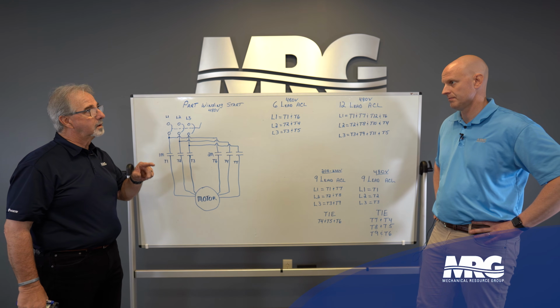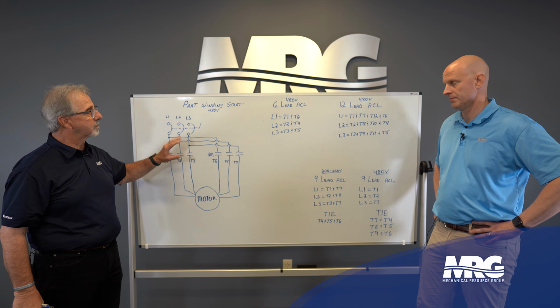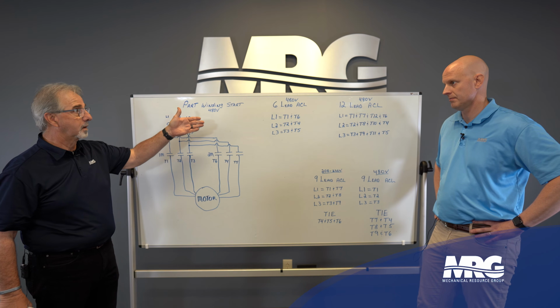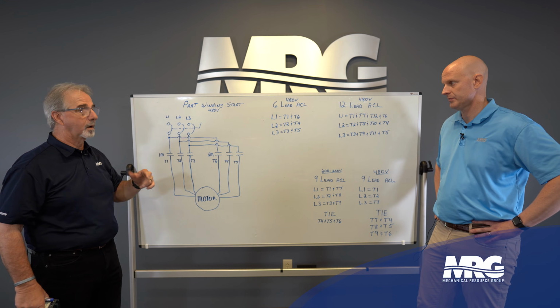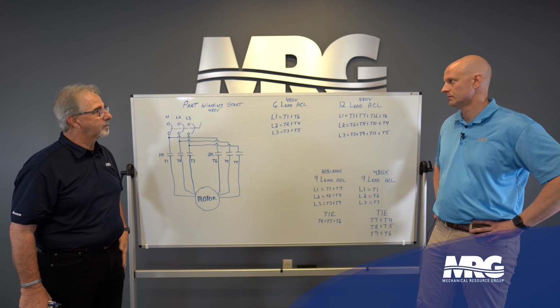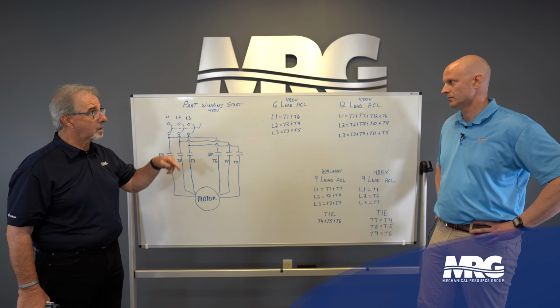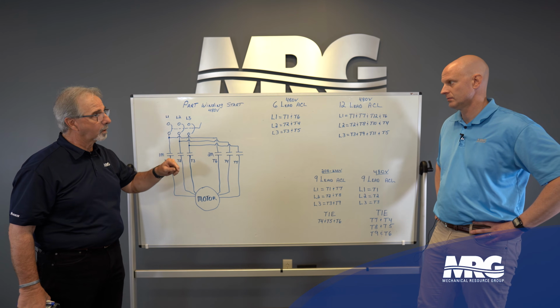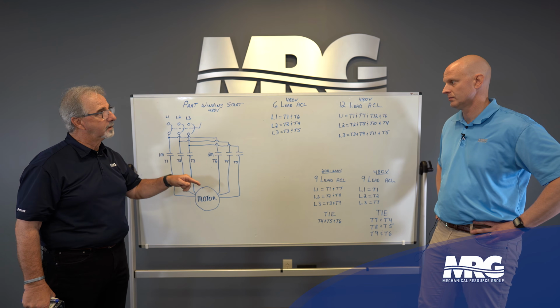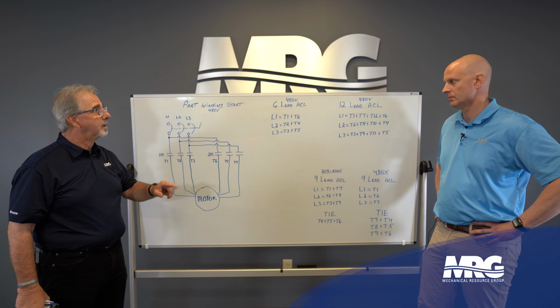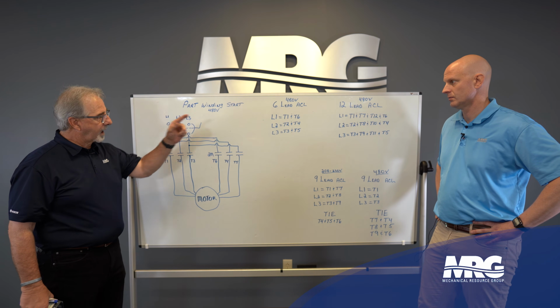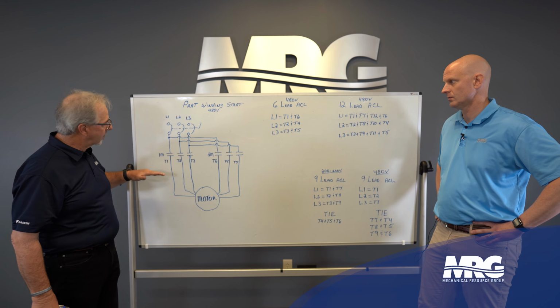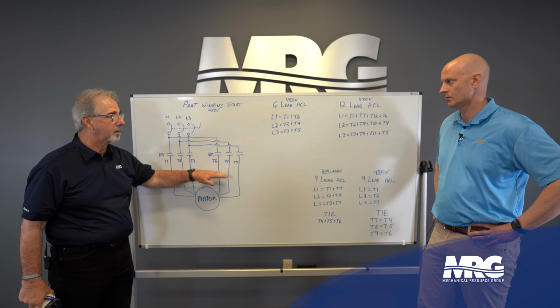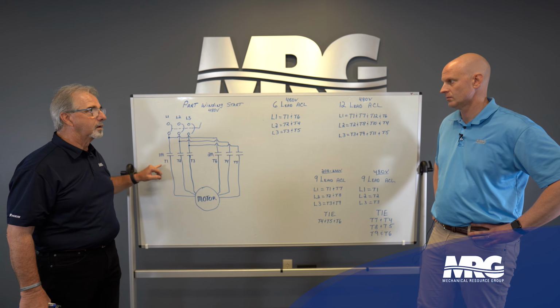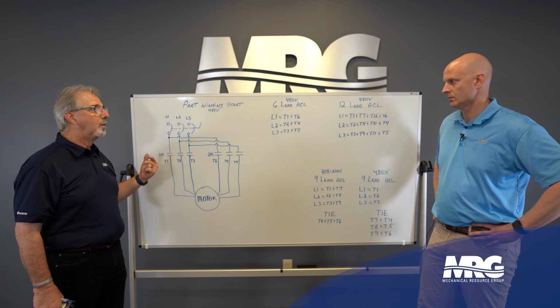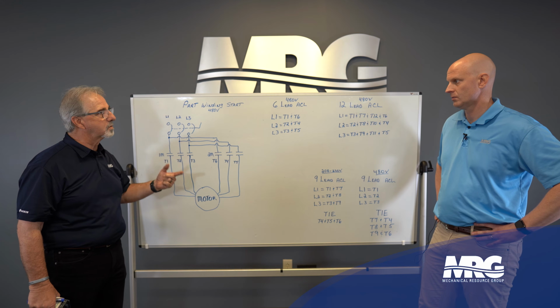What's important is that you understand this is on a 6-lead motor or a 12-lead motor. So I've given you across the line connections. If I was going to start this 6-lead motor across the line with a single contactor, L1 would be motor leads 1 and 6, L2 would be motor leads 2 and 4, and L3 would be motor leads 3 and 5. Those motor leads are numbered, but we have to remember that I have to stay in that configuration. If you look along the bottom of the contactor, 1, 2, and 3 are correct, left to right. But when we go over to the second contactor, remember leads 1 and 6 have to be on phase A.